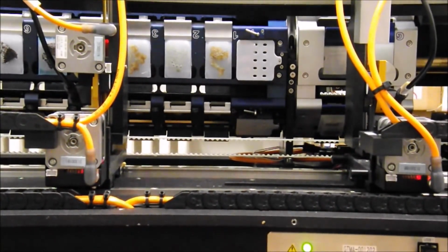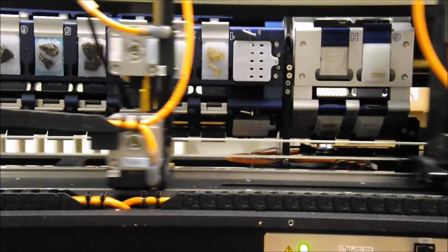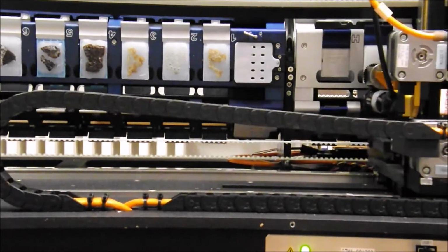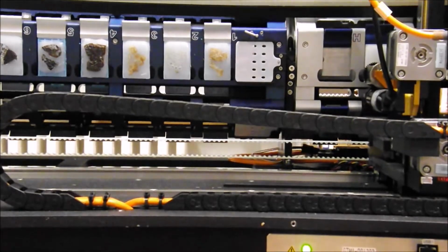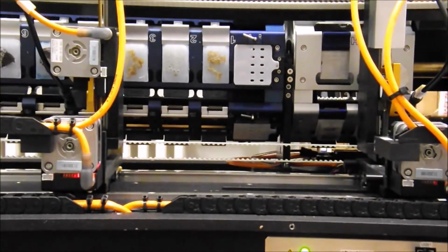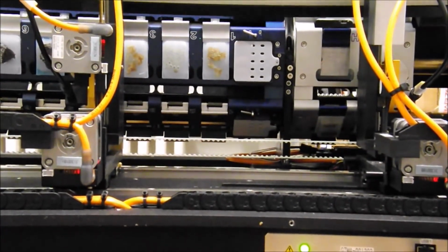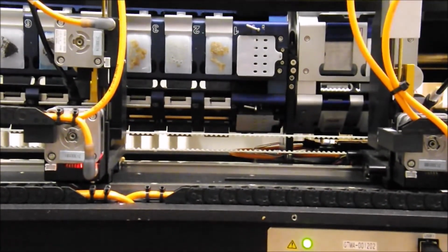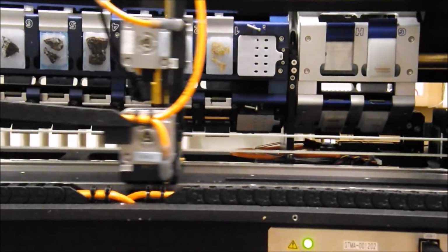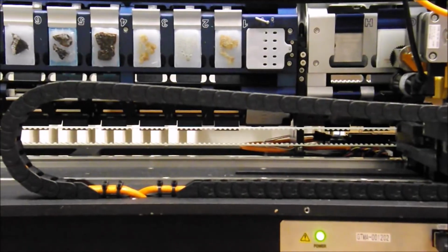After clicking Start, the TMA Grandmaster begins to work. Please notice that the TMA Grandmaster has a driller and a puncher unit. These units are working together at the same time. So, when the puncher unit is punching out a tissue core, the driller unit drills the hole for this given tissue core in the recipient block. That's why we can produce superior quality TMA blocks.